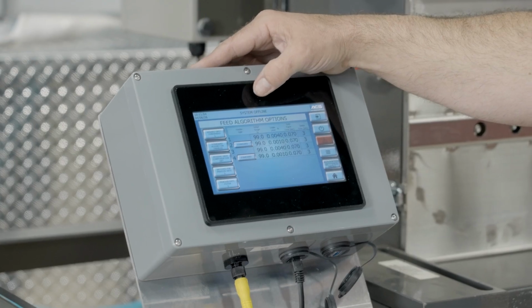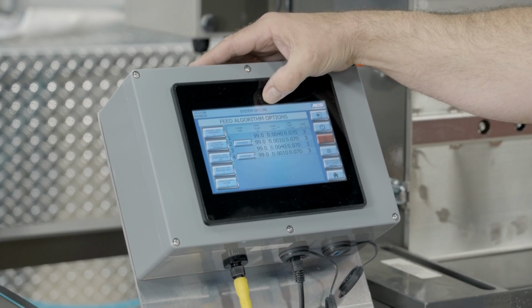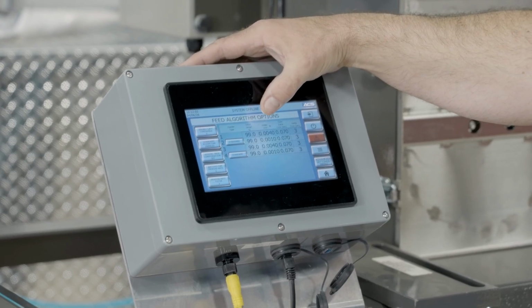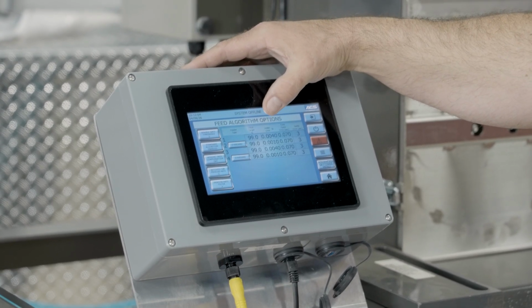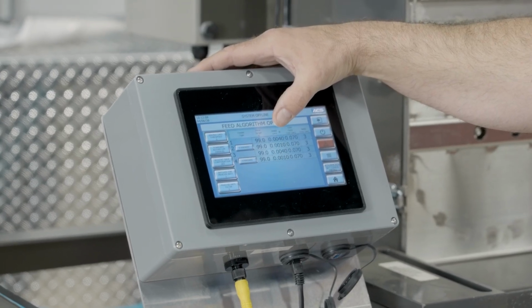We have that set to 99, so instead of opening for 4 seconds, we're going to open for 99% of 4 seconds. And then we look at our under limit to make sure that we're within that value of the target. So if our target's 1 pound and we're within 4 thousandths of 1 pound, we don't retry.